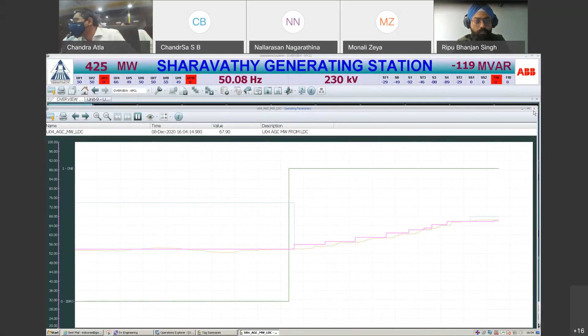So here we wanted to plot 2-3 parameters. The first signal is whether the AGC is switched on for this unit or not, that is the status, 0 or 1. If AGC is on, one signal will come. The next is what signal we are receiving from the state load dispatch center in Bangalore, and how our generator is instantly responding.